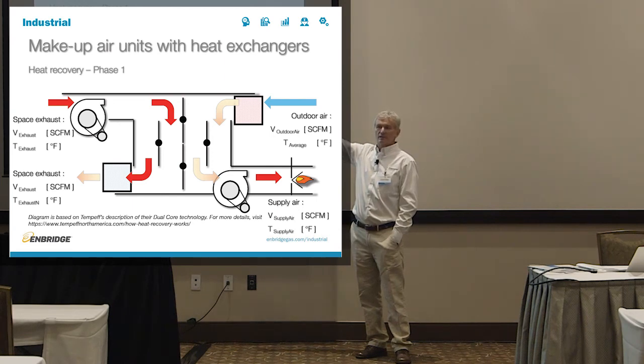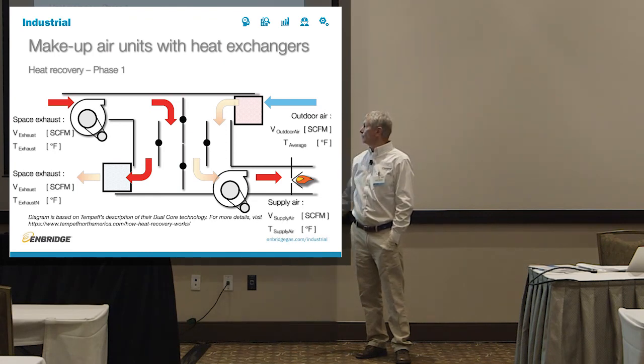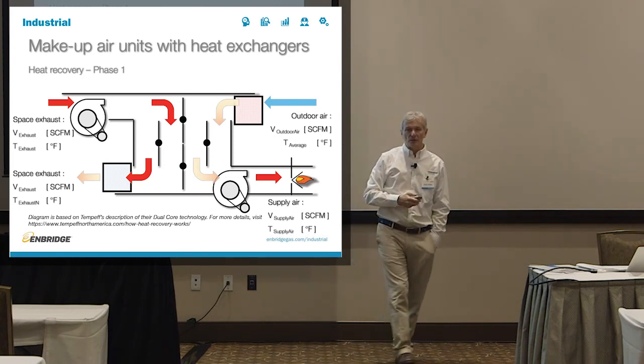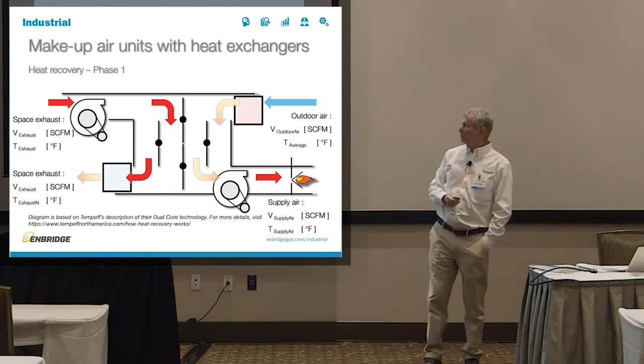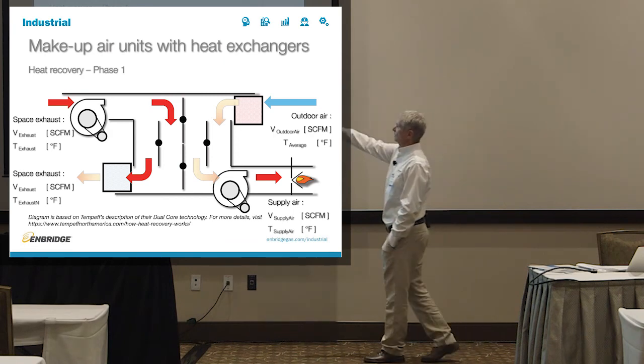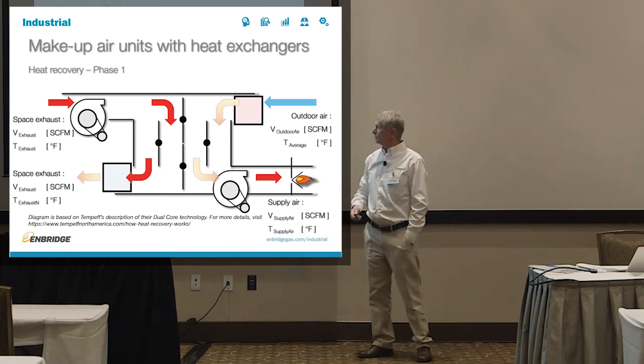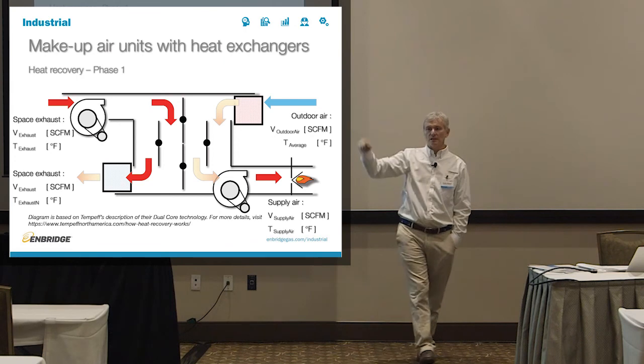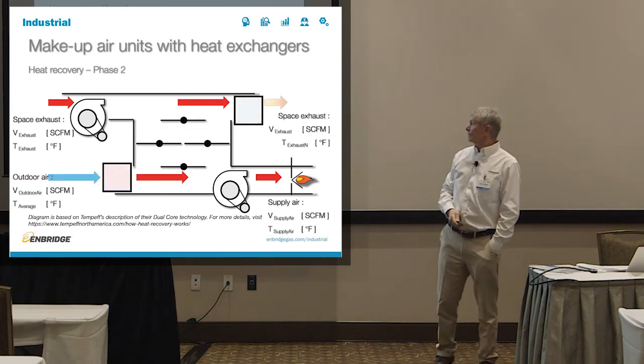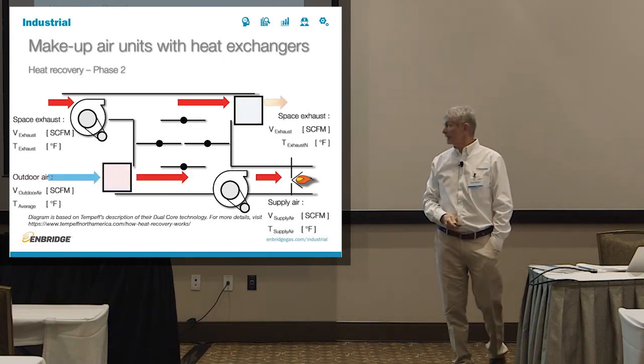Now, if your requirements are such that you don't need any burner, that's fine. You can use this unit without any burner. They sell it without burners. But if you need to add heat, they also incorporate a burner after this. The neat thing about it is, if you look at the dampers in the middle, this works like this for about 2 minutes, according to them. And then they switch it like this.